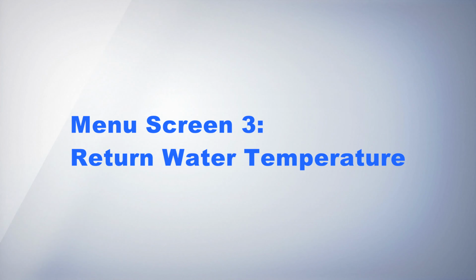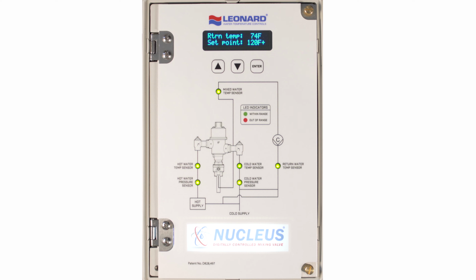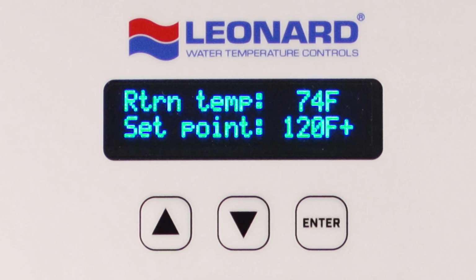Menu Screen 3. Return Water Temperature. Pressing down 3 times displays Return Temp, F or C. This screen displays actual return water temperature if the Nucleus is equipped with the optional return temperature RTD value as measured on T4. Note: a large negative value displayed at the return temp line is an indication that there is no sensor installed to the main control board, or the wiring to the main board is improper or the sensor is damaged.